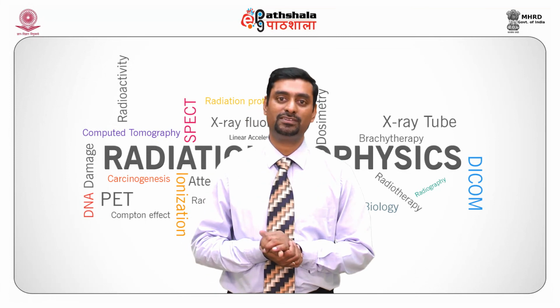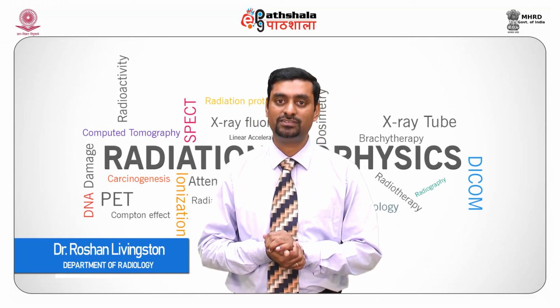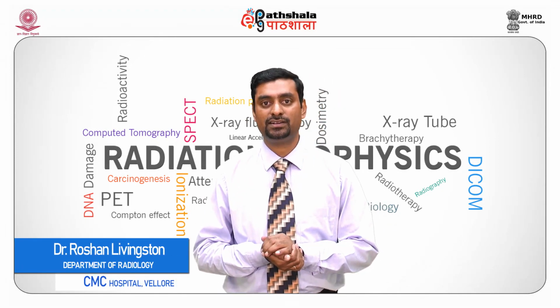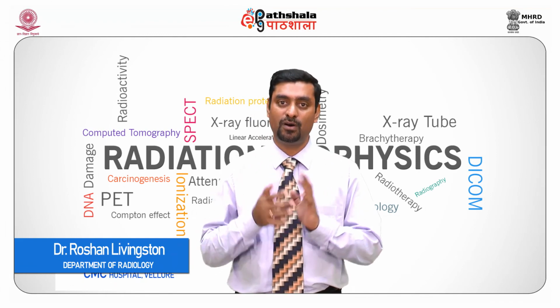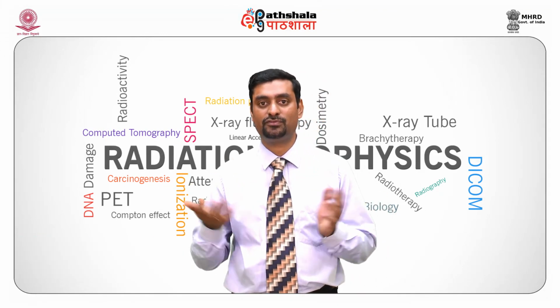In a direct flat panel system which has amorphous selenium technology, X-rays are directly converted into electrons to form an electronic image which can be used for diagnosis.